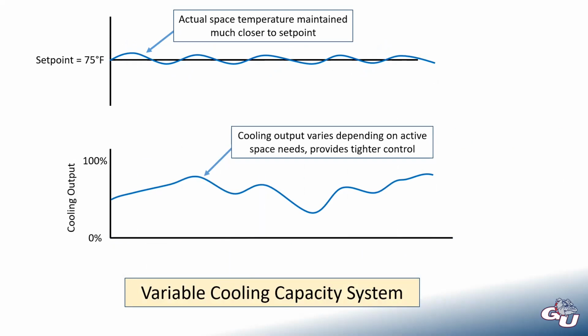And so if you have a conference room and people walk in, a big group of people for a meeting, let's say, then the cooling output will start to ramp up to a higher level. And then when everyone leaves, it'll ramp down. Or maybe throughout the day, if there's windows in that room, as the sun comes around and shines in the window. But this is one good advantage of a VRF, or really any variable capacity system, which there are many.